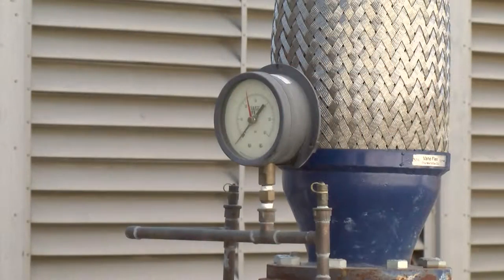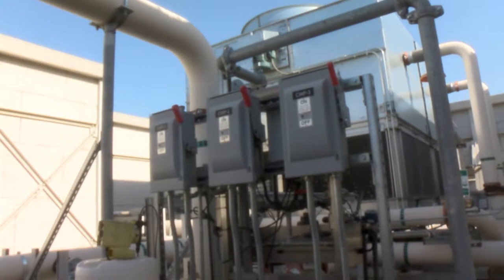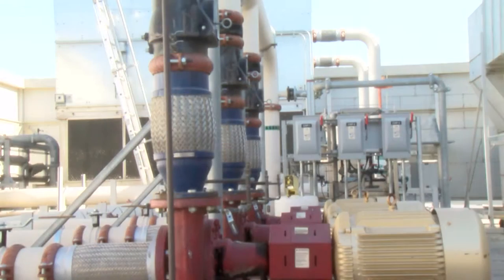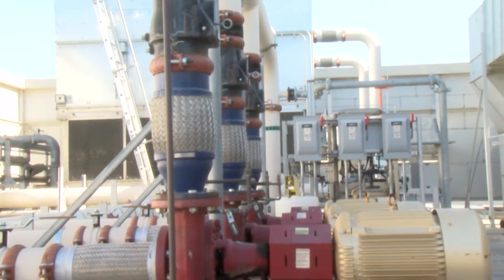Wow, that's a lot. So any idea what the cooling tower modifications will cost? You know, relative to the amount of water being used and the cost of that water, it's actually pretty relatively small. Usually for a cooling tower the size that operates this building, it's somewhere in the $50,000 to $100,000 range, with probably a payback period of maybe 5 to 10 years.